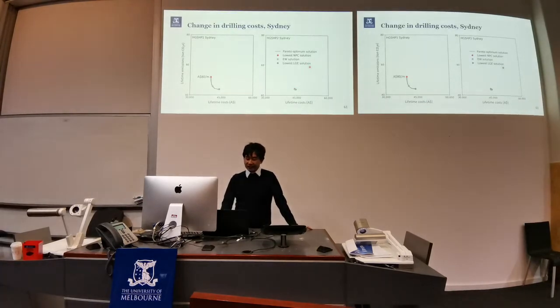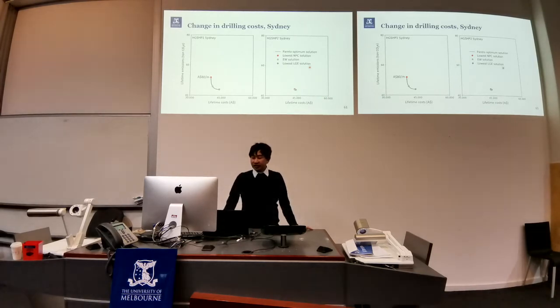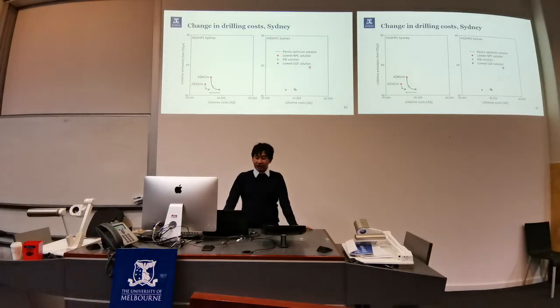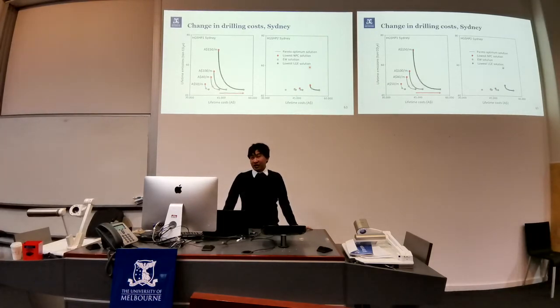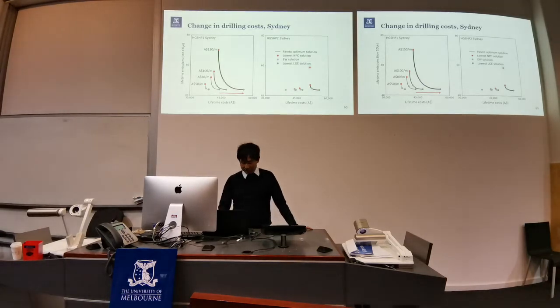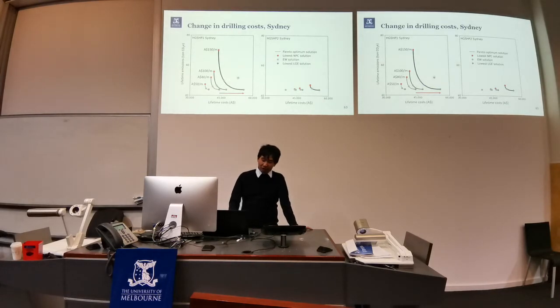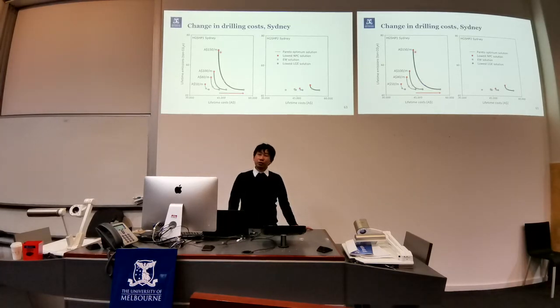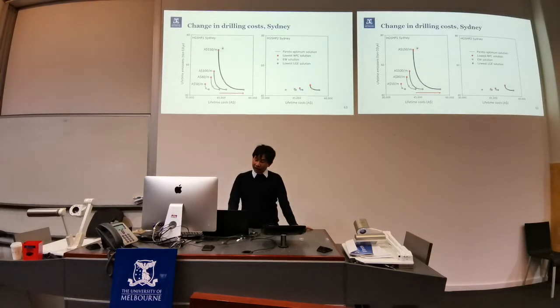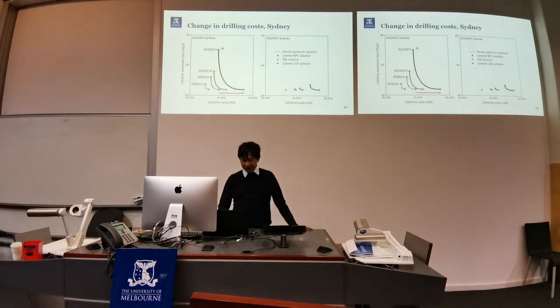Now, what happens if we change the drilling cost as before? So this is the case when the drilling cost is $80 per meter. When drilling costs get cheaper, the optimum solution range gets shorter, as the ground source heat pump system is preferred. When this gets more expensive, the range significantly widens to give you a lot more potential combinations with optimum share factor. However, the range most likely increases just because the lowest cost solution gets closer and closer to the conventional system. In fact, at this point, this is the conventional system in Sydney.